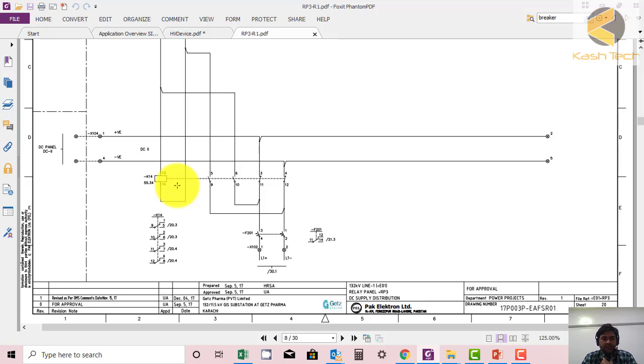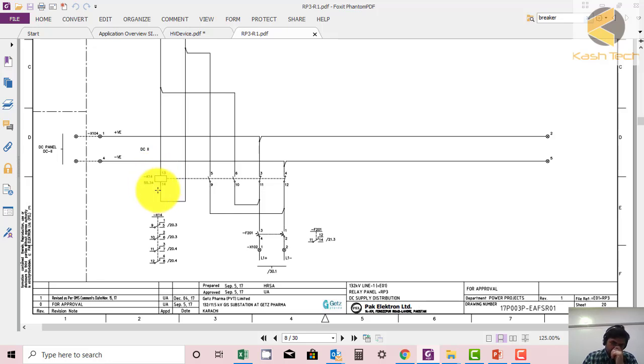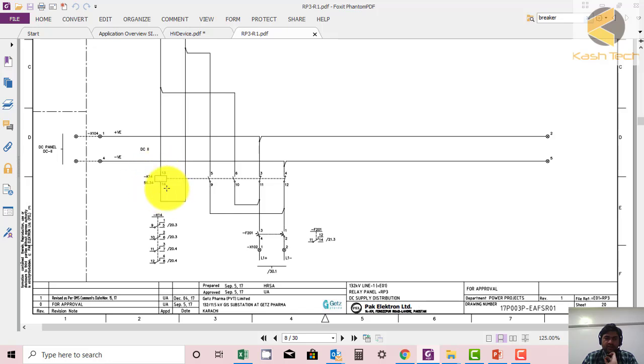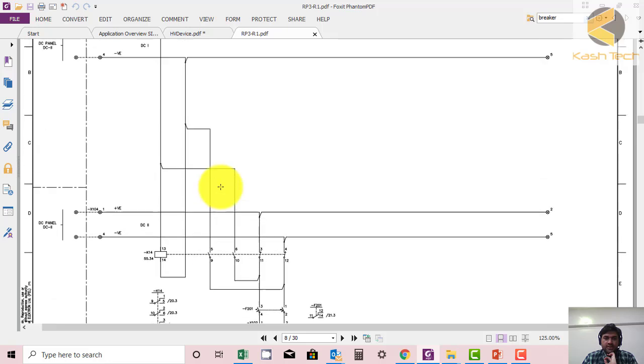You can see this - we are calling it an auxiliary magnetic contactor, or it could be auxiliary relay. There is a small difference: relay is a small transparent type and contactor is in black and more heavy, so you can check physically in the panel. But both function the same, so this is like an auxiliary relay, and these are the contacts of this auxiliary relay.